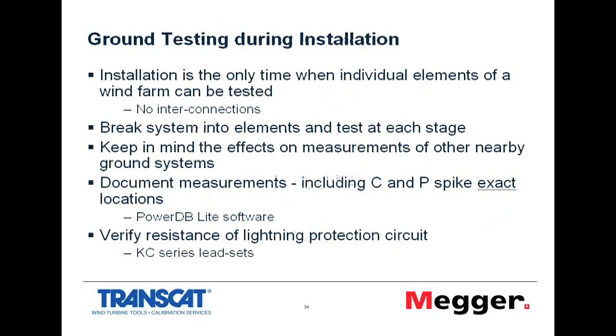Moving on now to ground testing during installation. Installation is the only time when it's possible to test and verify the performance of individual elements of a wind farm earth system, mainly because there are no interconnections at that point. We've installed maybe the base ground system on a single turbine, and we can make that measurement. It's important to break the system into elements and test at each stage to check and verify the performance of each part of the system.